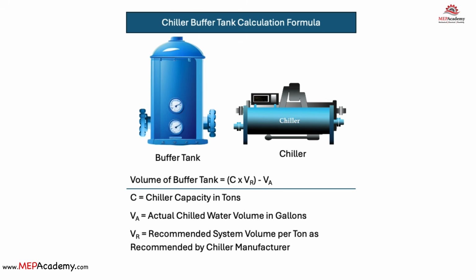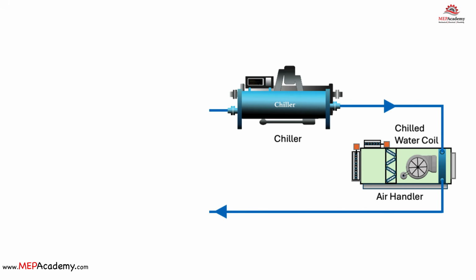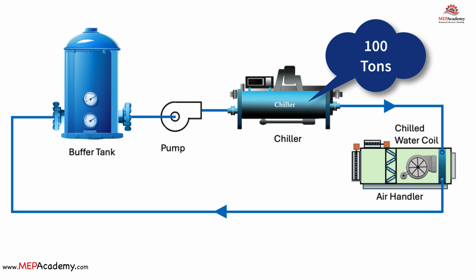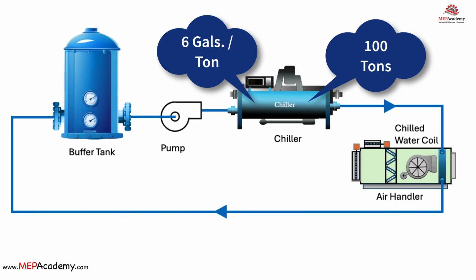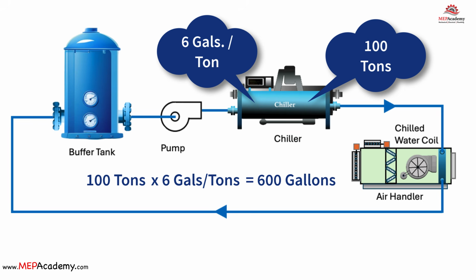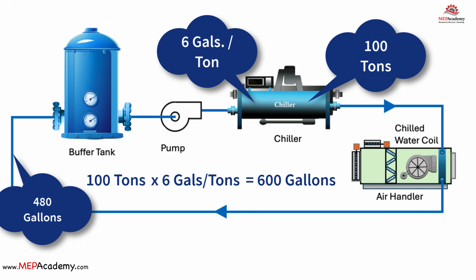We'll need to make up some values for this example. Let's say we have a small chiller of 100 tons and the manufacturer requires 6 gallons per ton minimum volume. If we use this information, we can derive a value at which anything below that value would require a buffer tank. 100 tons times 6 gallons per ton equals 600 gallons minimum system volume. If the actual system volume is less than 600 gallons, then a buffer tank becomes required. Let's say our system volume is 480 gallons.